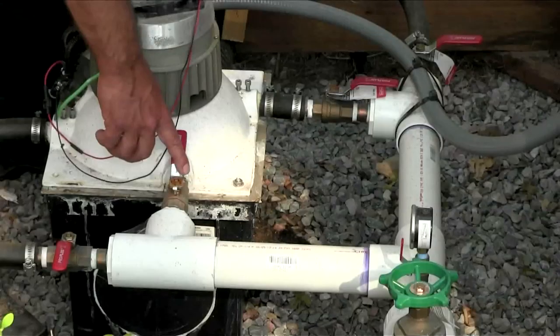You need to watch and make sure that the screen on the intake is cleared. In this case, everything's underground and super maintenance-free. Every two or three years you may have to change bearings depending on how hard the turbine is running. This four-nozzle turbine is a little bit overkill on this site and would produce about 1,000 watts under ideal conditions. The homeowner closes two of the nozzles and operates closer to their needs — still overproducing, but not so much that the turbine is getting unnecessary wear and tear. So turbine bearings, cleaning the screens, and general inspection occasionally is all that's needed.